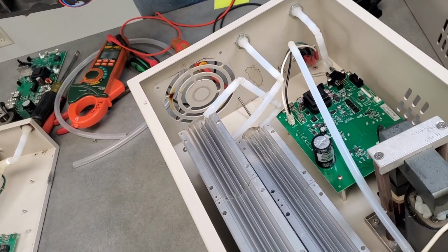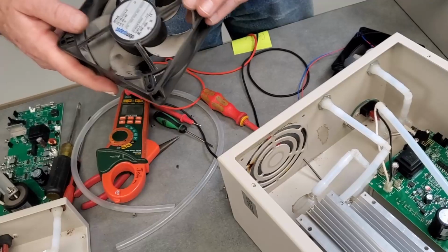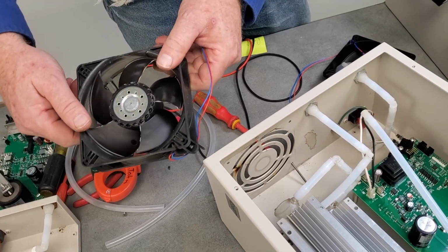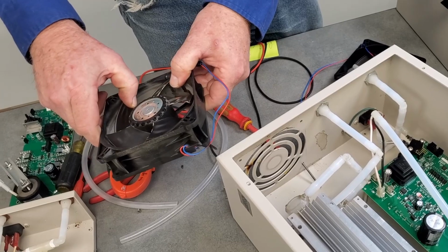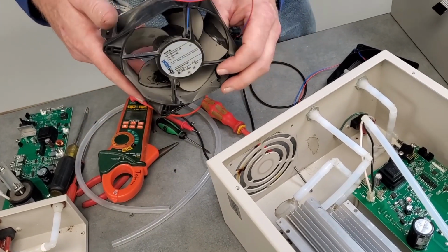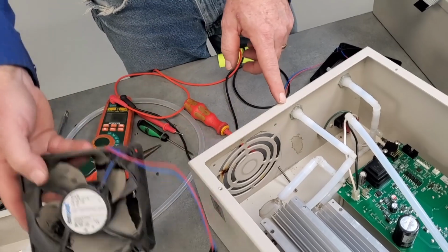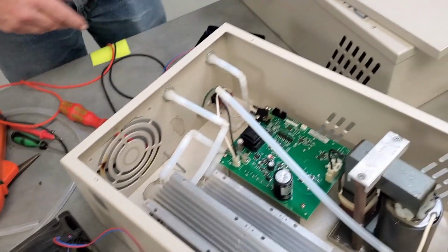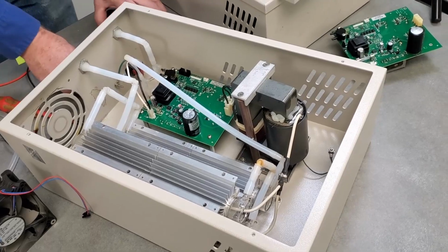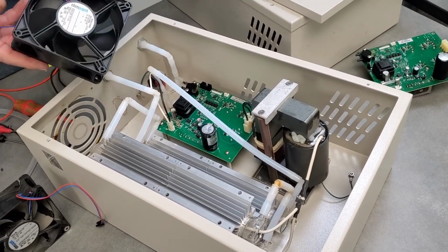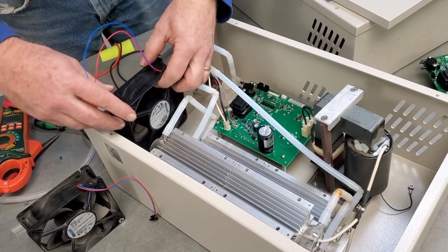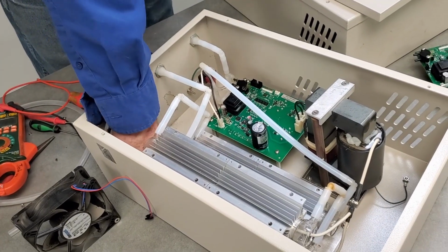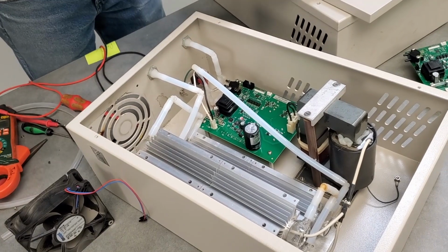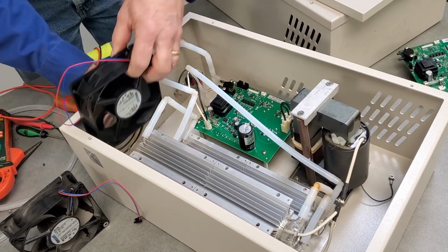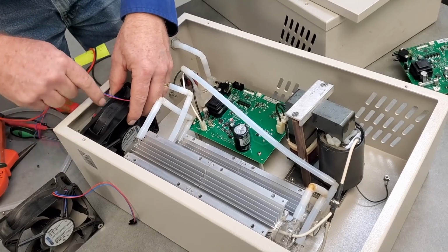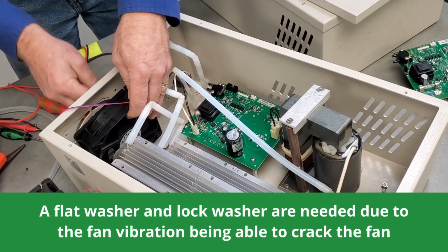So sometimes if you get a little bit of water or something on the fan, I don't see indications of much damage, but you know, if you're inspecting your generators, the fan is going to be pretty important. If you see one that's not operating, we want to make sure we get that replaced so that it keeps things cool and doesn't result in a bunch of other problems. Let's see, which way did this go? I think it's blowing in, so we've got it oriented right. Get these parts out of here. There are little arrows there to tell you which way the air is blowing.